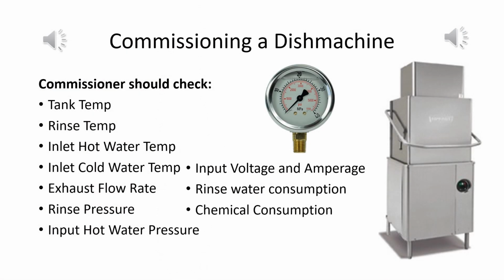Section 1. Commissioning. Properly commissioning the dish machine is probably the most important step an operator can take to ensure that their hot water system stays efficient for as long as possible. Upon installation, the commissioner should check the tank temperature, the rinse temperature, the inlet hot and cold water temperatures, the exhaust flow rate if there is an exhaust hood in the dish room, the rinse pressure, the input hot water pressure, the input voltage and amperage, the rinse water consumption, and the chemical consumption.